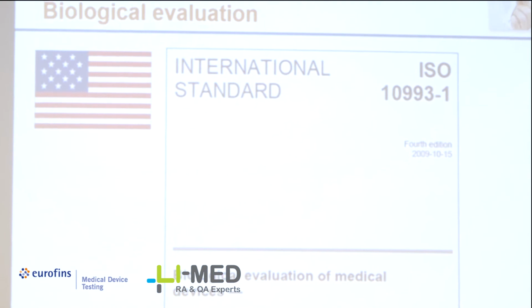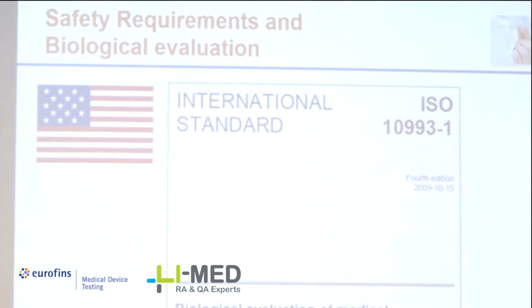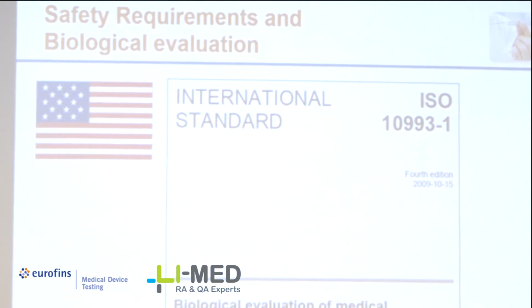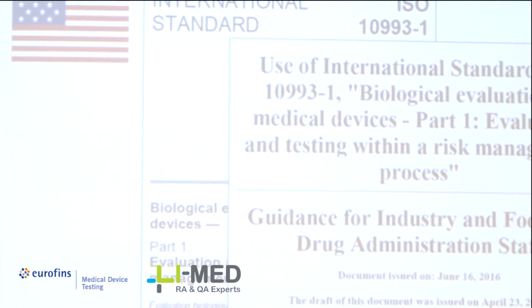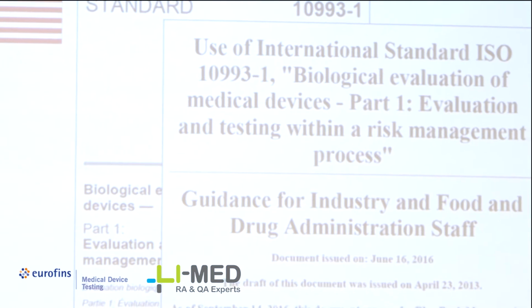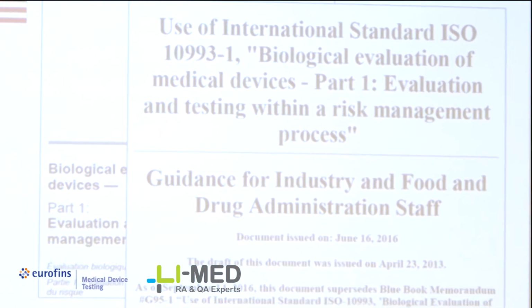But if you are going to the US market, you need also to consider that the ISO 10993 is not sufficient, because you should also consider the guidance that FDA issued 2 years ago about the use of ISO 10993-1, because FDA has its own interpretation of the standard and provided also additional requirements for biocompatibility. That's why you should consider both of them.